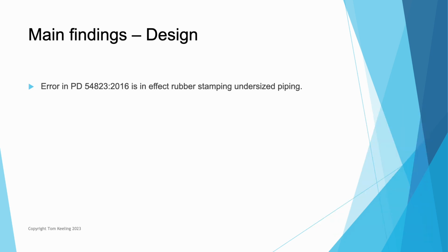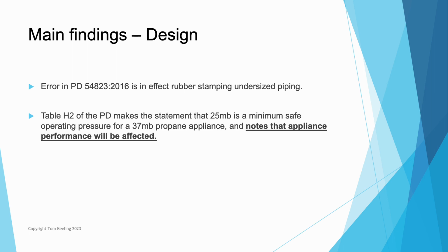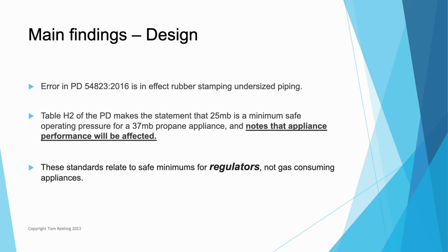So there is an error in PD 54823 2016, which is in effect rubber stamping undersized piping by permitting low pressure at an appliance. Table H2 makes a statement that 25 millibars is a safe minimum for a 37 millibar appliance, but it does note the appliance performance will be affected. However, when you look at where the information is taken from, the standards relate to a safe minimum for a regulator to operate at, not a gas consuming appliance.